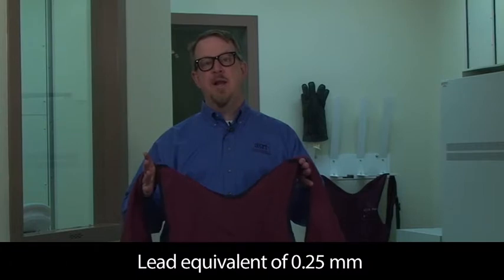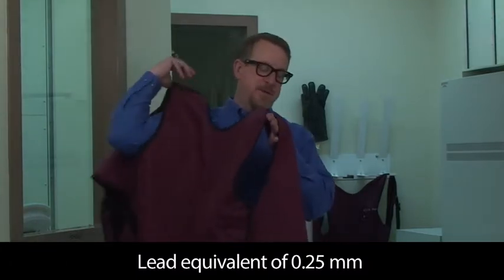The term lead shield can be misleading because many shields are no longer made of lead, but instead use a lighter weight composite of other metals such as tungsten or tin at a thickness that's equivalent to the properties of lead. Lead shields come in different shapes and sizes to protect certain body parts. The most frequently used apron is the body apron, which must be at least a lead equivalent of 0.25 millimeters.